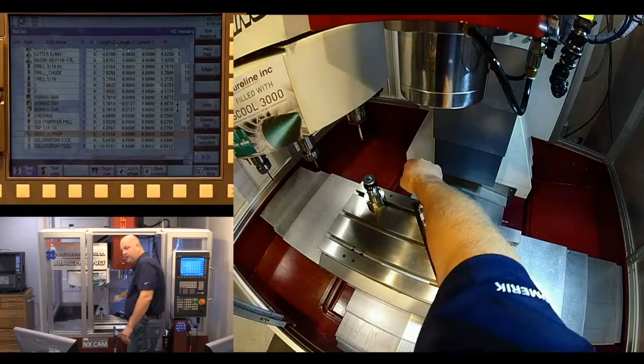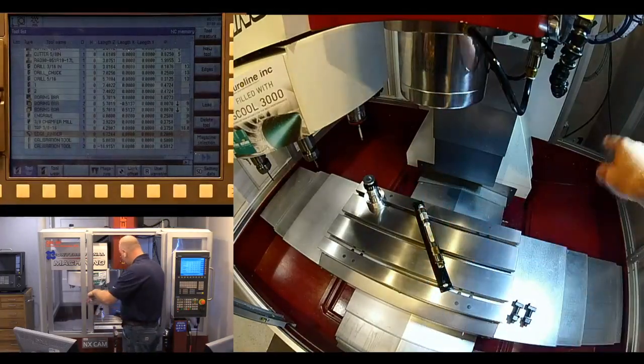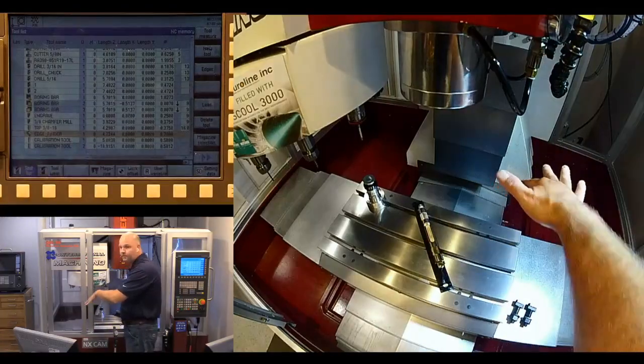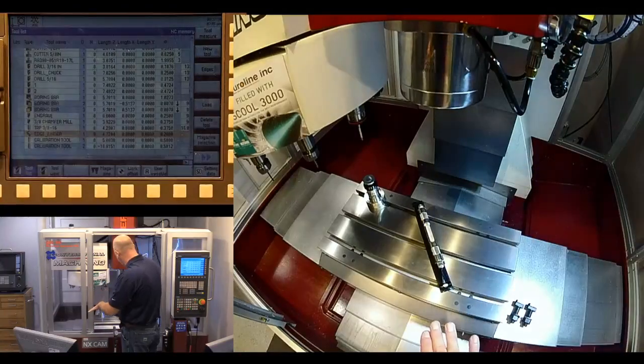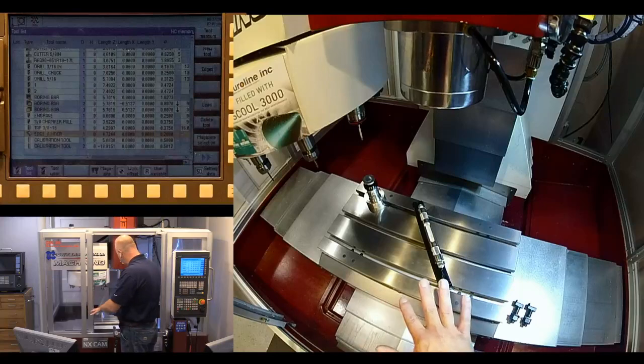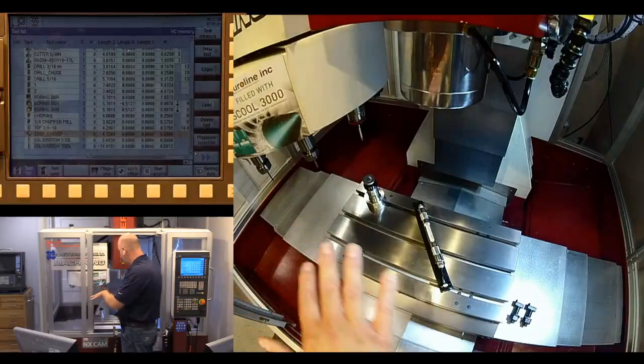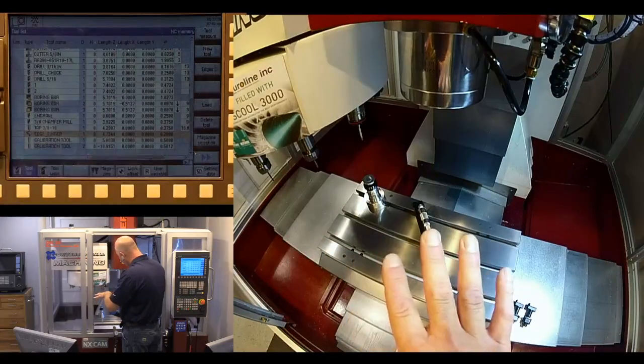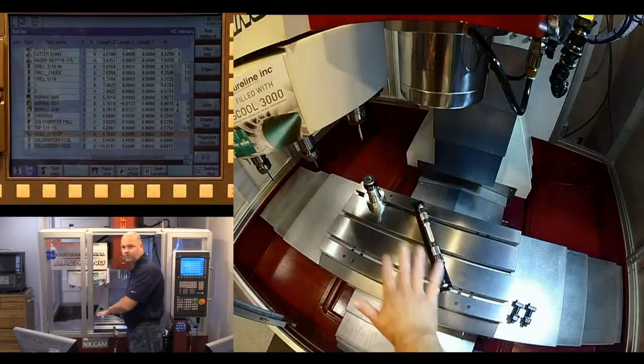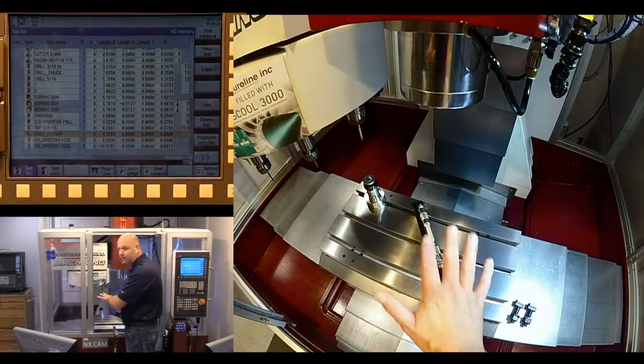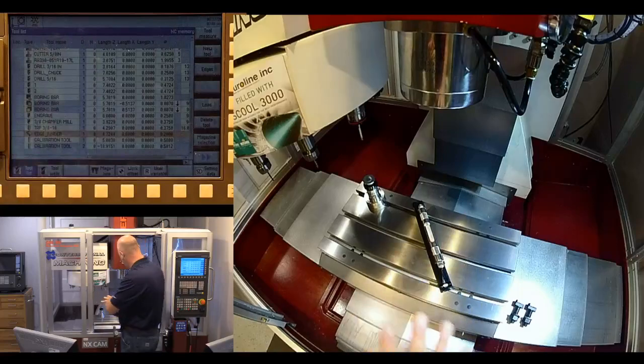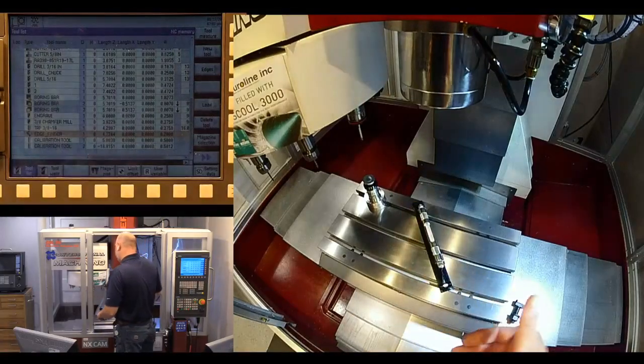What happens is when I go to loosen the back pad, I have some other leveling pads that I could start teetering on. If I'm always loading, the worst I'll get is I move away from the other pads. But if I go the other direction, I don't know if I'm putting too much weight on those pads and the machine starts teetering or rocking.